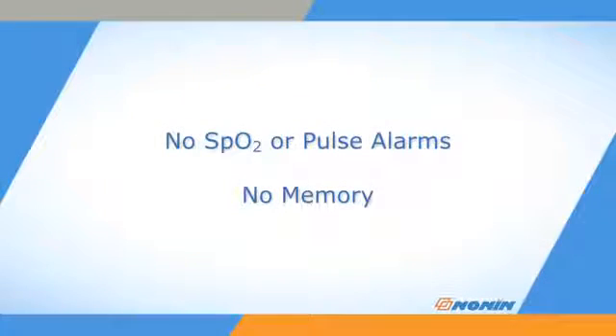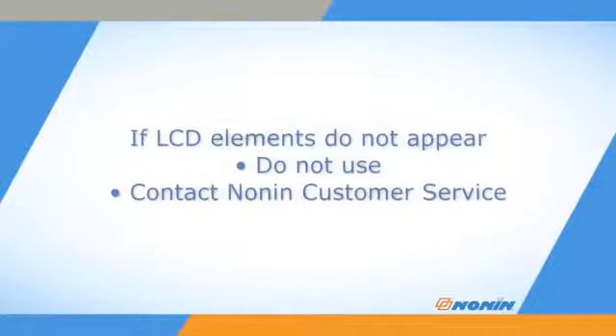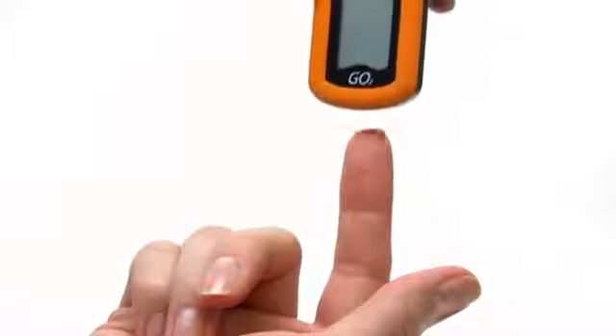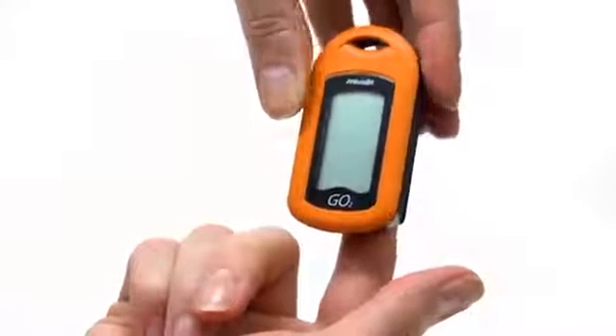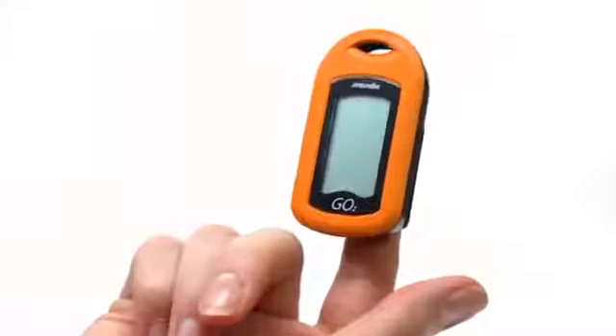The GO² oximeter does not have alarms and is designed for periodic spot checks. It also does not have any memory. If any LCD elements do not appear or if any of the displays do not appear as expected, remove the unit from use. If the screen remains blank when you insert your finger, check that the battery is inserted properly and that the finger is warm, or try a different finger.